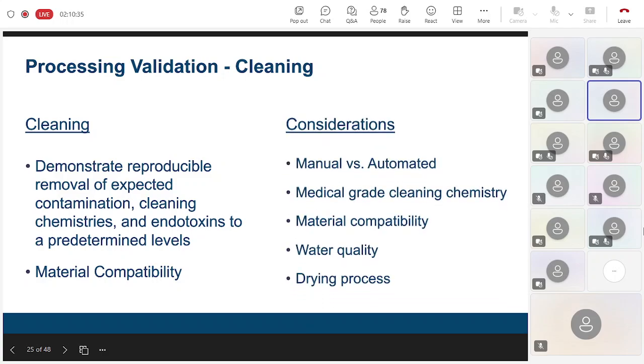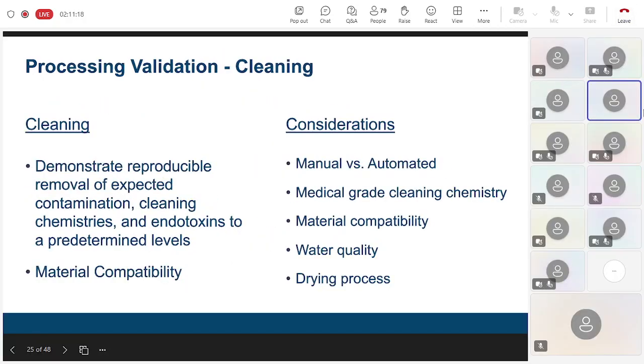The process should consider whether we are going to have a manual or an automated process. Are we going to just wash the device in the sink, or are we going to place it in the washer disinfector or the ultrasonic machine? We need to ensure that medical grade cleaning chemistries are used. These cleaning chemistries have been designed and tested for surgical instrumentation, and they rinse freely from device materials. So using dishwashing detergent or things like that are not what we require for cleaning of surgical instruments and 3D printed devices.